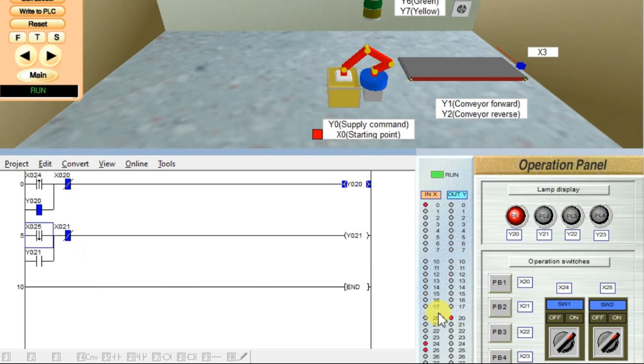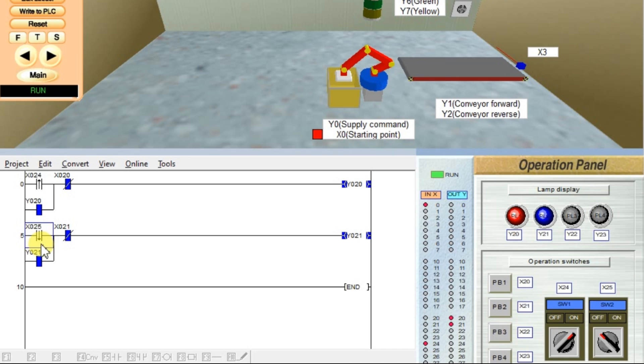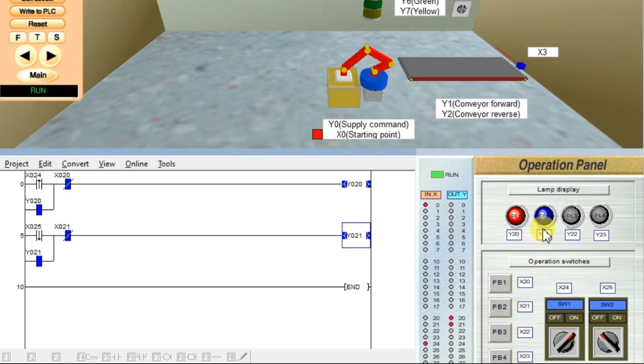So X25 now is in ON condition. I will make it OFF. That means I will change the state from 1 to 0, OFF. 1 to 0. As this is a falling edge, it will only activate the output when there is a change from 1 to 0. Now it will activate the output Y21. See, Y21 lamp is ON.